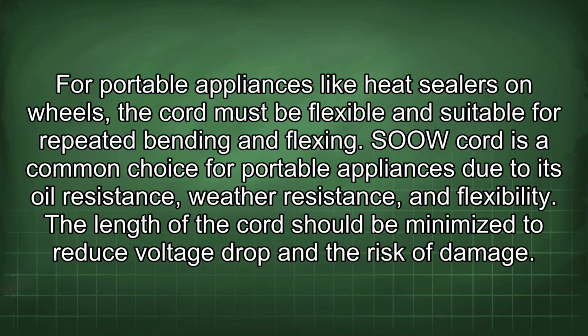For portable appliances like heat sealers on wheels, the cord must be flexible and suitable for repeated bending and flexing. SOOW cord is a common choice for portable appliances due to its oil resistance, weather resistance, and flexibility. The length of the cord should be minimized to reduce voltage drop and the risk of damage.